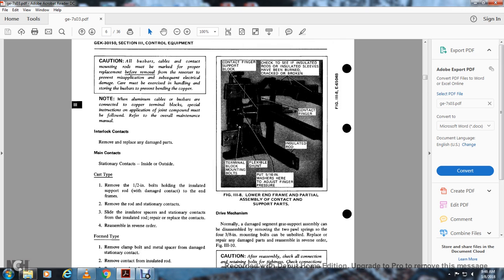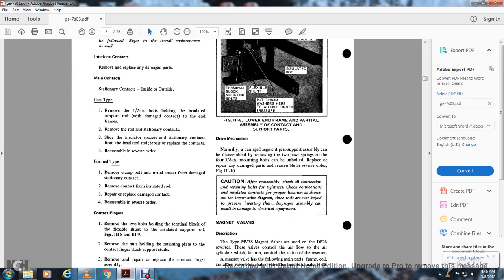Figure III-8 shows the lower end of the frame partial assembly with the contact support parts. Contact finger support block: check to see if the insulated rod's insulated sleeves have been burned or have a crack. Contact finger insulated rod: use 5/16 of an inch washers under the head to adjust the finger pressure. Flexible shunt, terminal block, mounting bolts.